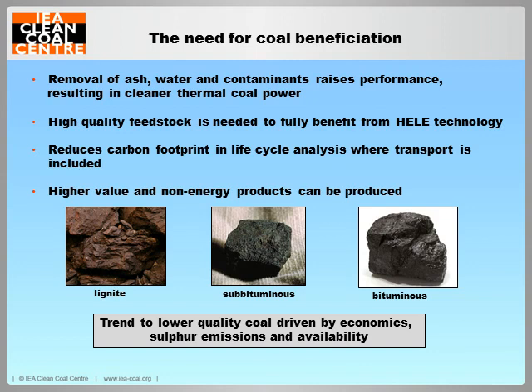And part of the reason for the switch to PRB coals in the United States. Water in the fuel has a greater thermal load in a plant than the mineral content. The formation of ash can increase boiler fouling that impacts the reliability of a station. Removal of contaminants such as sulfur and mercury can mean simpler pollutant control, consuming fewer chemicals in the effluent treatment plant. But a fuel with a higher energy content can mean an increase in primary NOx emission.